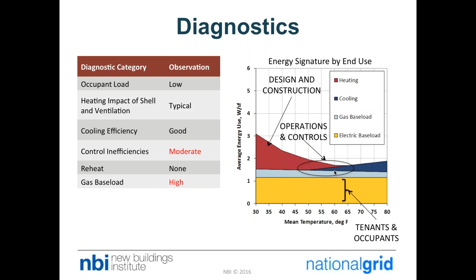And in fact, First View can tell you a lot of what those things mean. The slope of that heating slope will tell you about insulation and about infiltration. When you see things like this where it is heating and cooling at the same time, that tells you there's something wrong with your controls. If your band for the electric baseload is very large, that tells you something about how the tenants are occupying the space. And First View can go in and give you some automatic diagnostics about what might be going on in that building.